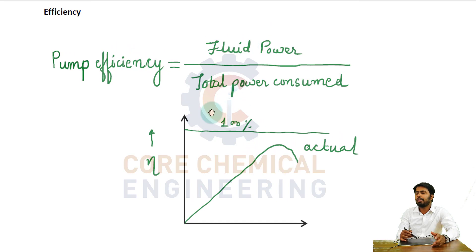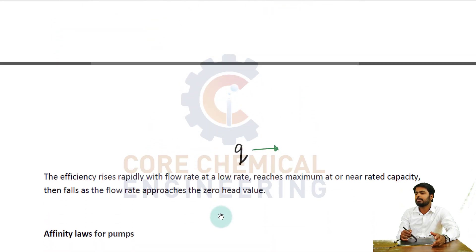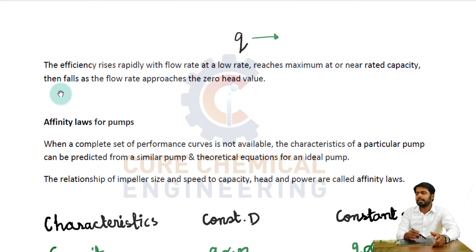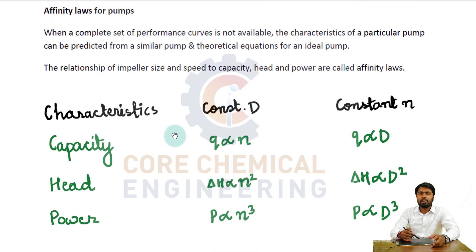Pump efficiency is fluid power divided by total power consumed. The efficiency versus flow rate curve shows that efficiency rises rapidly with flow rate at low flow rates, reaches a maximum at or near rated capacity, then falls as the flow rate approaches the zero-head value.